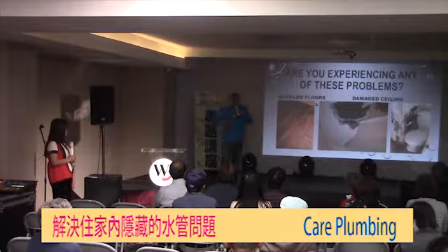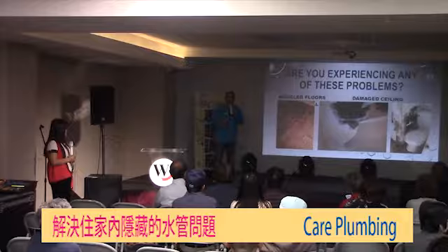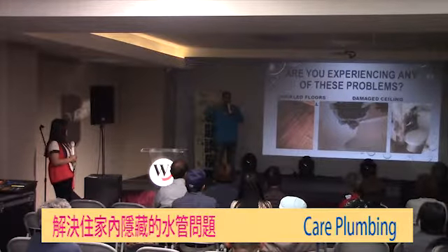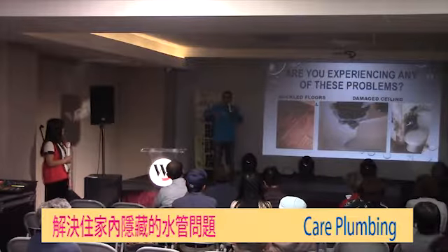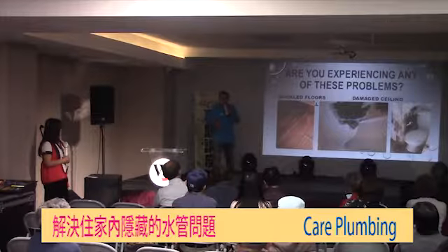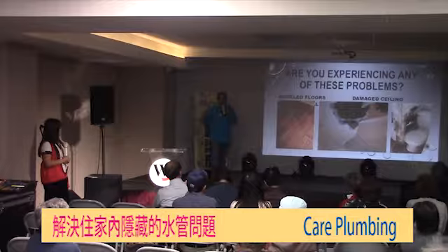99% of the time that would be a leak from your hot water pipe. It injects the hot water under the slab and it heats up the slab. Whenever you walk around the house and all of a sudden you come to a point where you stay and it feels warm, you definitely have a leak from your hot water pipe.